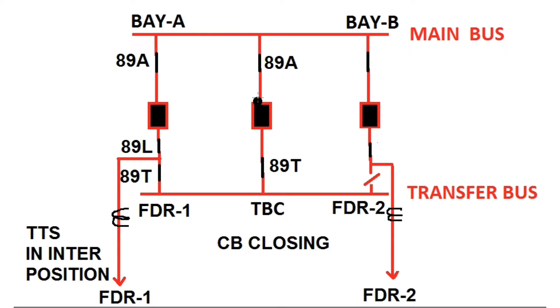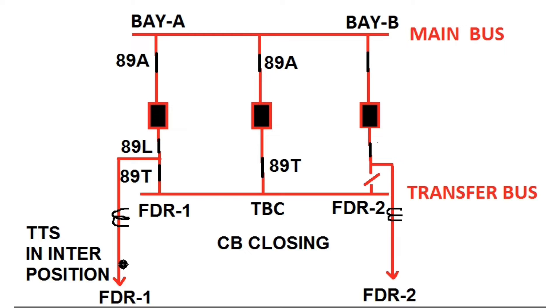After the TBC breaker is closed, the main bus and transfer bus are coupled by this TBC bay. Now 89T is closed, so these two bays will be in parallel condition. Now we can open the breaker of feeder 1 and power will be diverted via the TBC bay towards the main bus. Feeder 1 will get power through the main bus, through the TBC, then through the transfer bus, and via this isolator power will go to feeder 1 uninterruptedly.